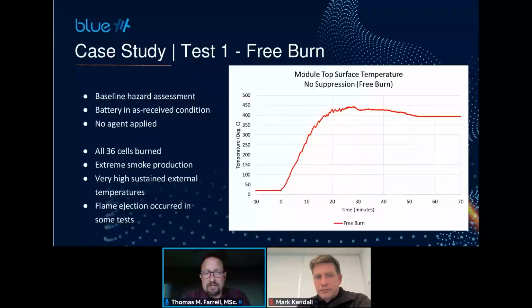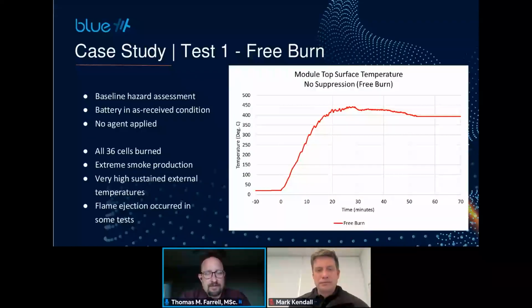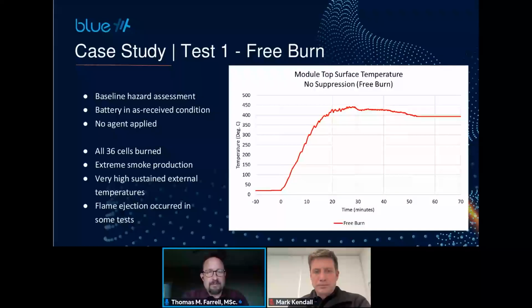What's also interesting is that the temperatures generated were sustained for a very, very long time. Once we did this test, we let this module sit for about 24 hours before coming back to it. Even at the 24-hour mark, the surface temperatures were still in excess of 100 degrees Celsius. So if there was another module nearby, above or to the side, it likely would have also been triggered into thermal runaway just because of the heat load radiated from the surface. We did this test several times, and in several of these tests, even though the battery was designed for containment, flame ejection still occurred.